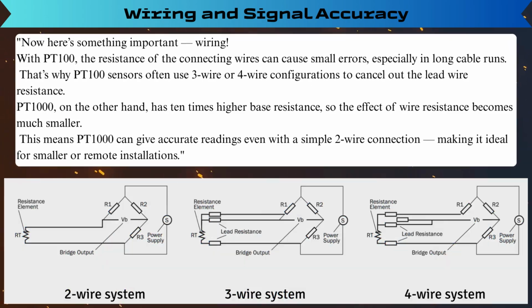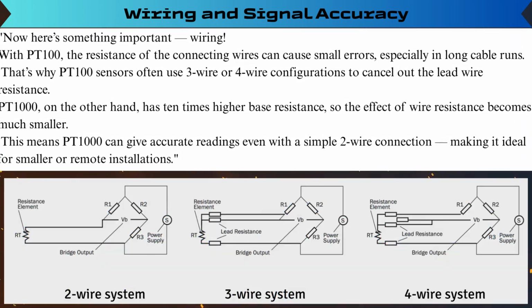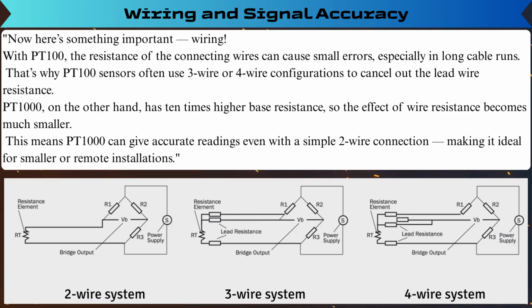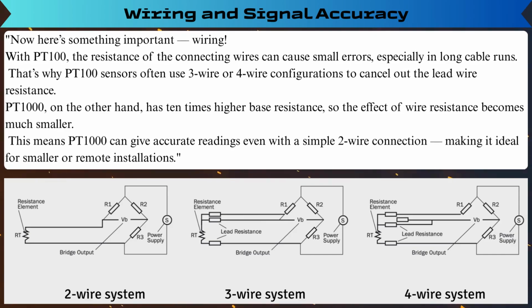Wiring and signal accuracy. Now here's something important: wiring. With PT100, the resistance of the connecting wires can cause small errors, especially in long cable runs. That's why PT100 sensors often use 3-wire or 4-wire configurations to cancel out the lead wire resistance. PT1000, on the other hand, has 10 times higher base resistance, so the effect of wire resistance becomes much smaller.